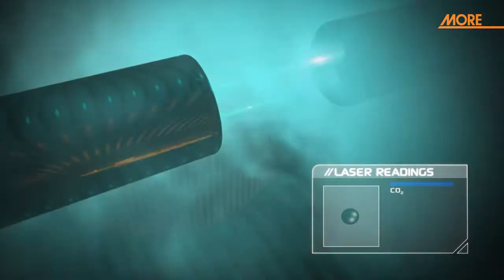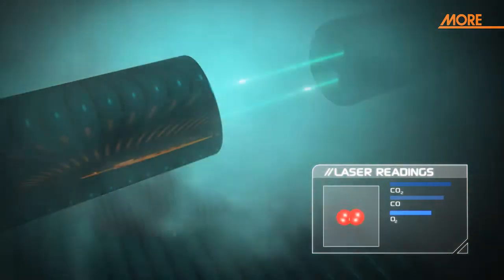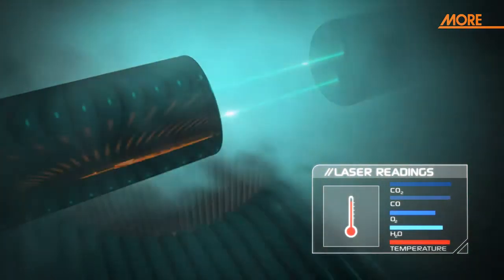The LINDARC recovers this energy and transfers it to the process. The laser units are installed on the fixed duct to analyze the core of the off-gas stream and measure the concentration of carbon dioxide, carbon monoxide, oxygen, water content, and off-gas temperature.